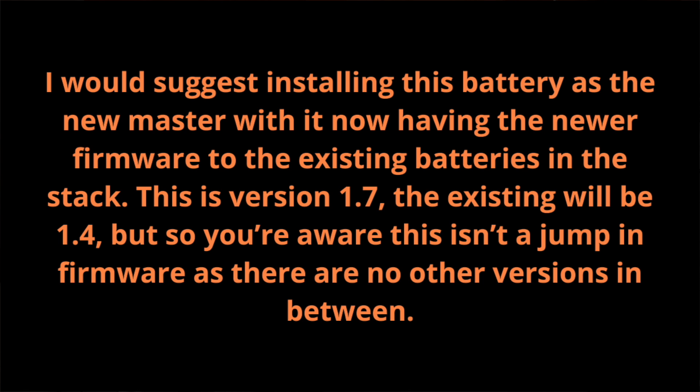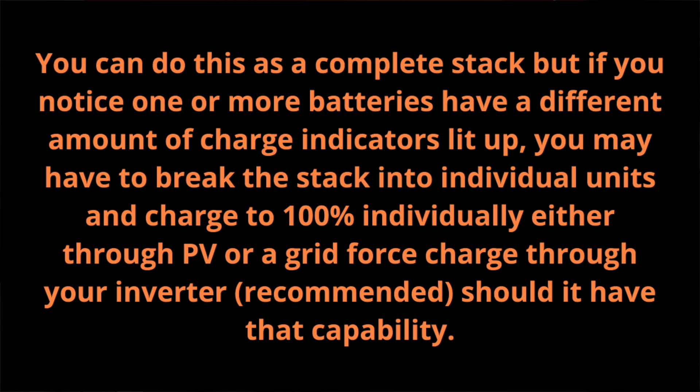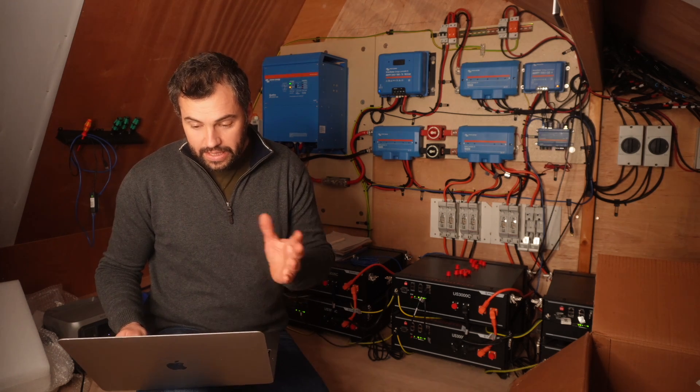So you're aware this isn't a jump in firmware as there are no other versions in between. The battery we have sent back will be as close to 100% SOC, give or take a few percent potentially lost with shipping time. To ensure the whole system will be balanced exactly, please charge your existing battery to 100% also before reintroducing this one. You can do this as a complete stack, but if you notice one or more batteries have a different amount of charge indicators lit up, you may have to break the stack into individual units and charge 100% individually either through PV or a grid force charge through your inverter recommended should it have that capability.